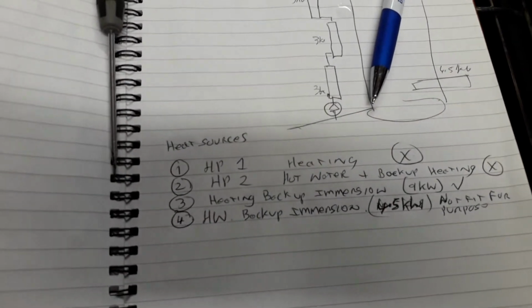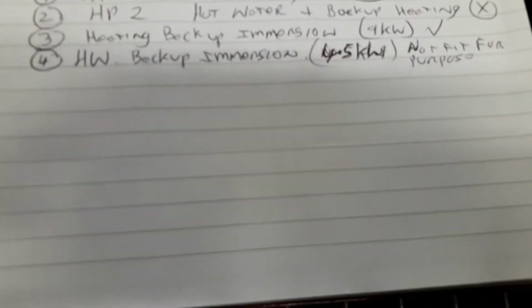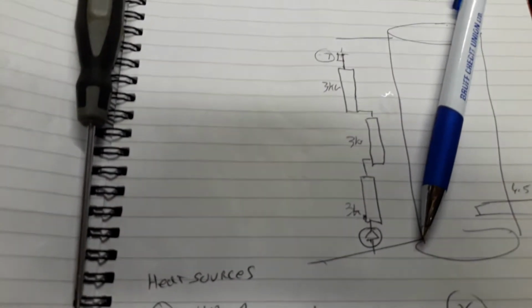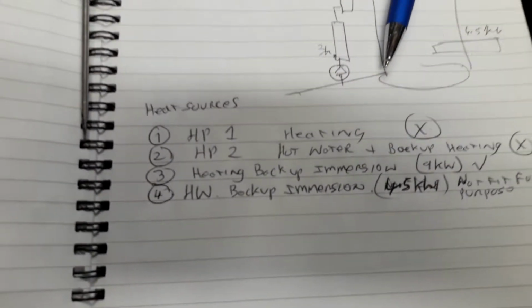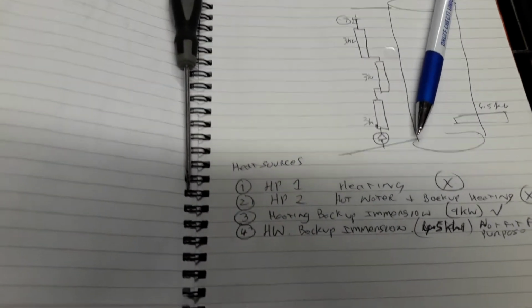With regard to understanding the problem, one possible quick fix is to add an external heater, which would cost about €500 or so, to the hot water cylinder, which would get us by quickly, and between Mike and the resources that are readily available, we could possibly do that in the next few days from now. Medium term then, after getting these things going, it should look at putting in a gas boiler as backup in case this ever occurs again.